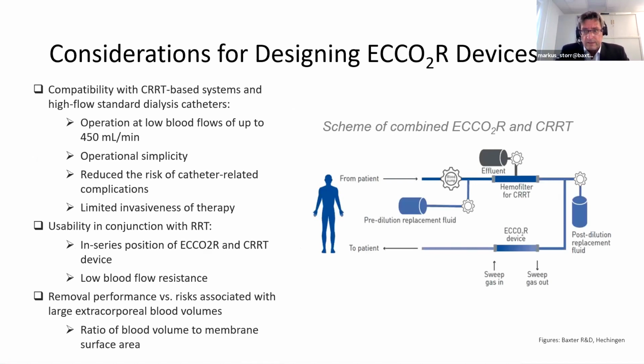PrismaLung Plus is a device that can be integrated into a CRRT system, in particular into our Prisma CRRT system, which is able to process a blood flow of up to 450 mL per minute. That means that the device design had to be tailored to operate efficiently at such low blood flow rates. The advantage of this setting is, of course, that we can use smaller catheters than required for ECMO, which reduces the invasiveness of the therapy and also reduces the risk of catheter-related complications.